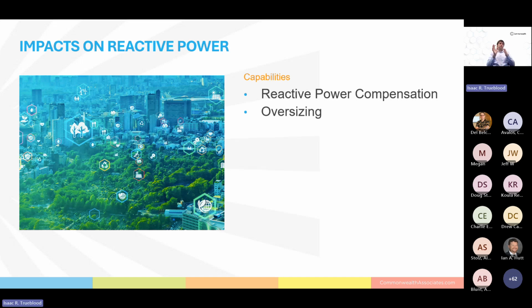A useful baseline, used in FERC Order 827, even though that is a transmission-based standard, is a requirement for inverters to dynamically produce power at a power factor between 0.95 lagging and 0.95 leading. To put it in simpler terms, an inverter-based resource, or any resource, that generates 100 megawatts of power at the point of interconnection is required to dynamically produce or consume 33 MVARs of reactive power at that point of interconnection. Each distributed energy resource will have specific standards that will be dependent on their distribution owner and their individual interconnection agreement with that distribution owner.